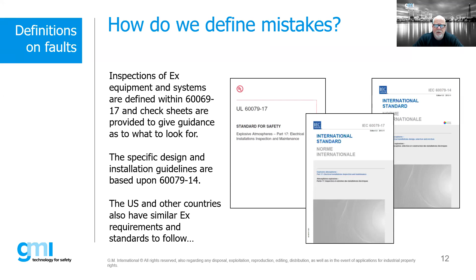Here's an example of what you'd actually find in the -17. This is a sample inspection sheet that when I go out to a site doing my EX inspections, we use these types of charts. It's very handy and good for everybody to understand. The way we want to read it: if we look at that first line - is the equipment appropriate to the EPL zone requirements of this location?